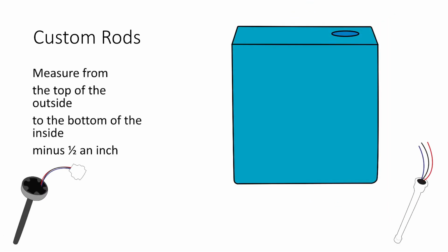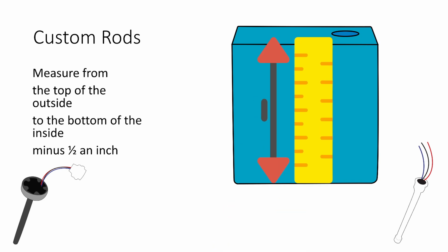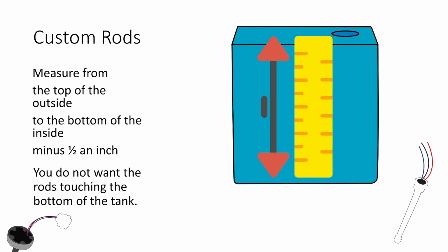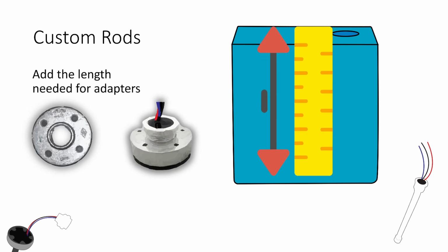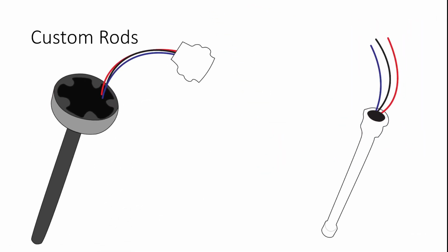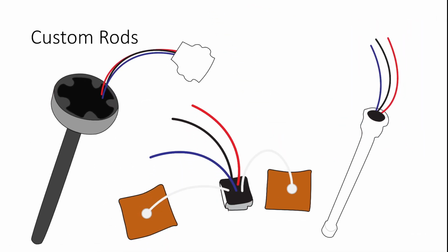To measure the height of the rod, measure from the top of the outside of the tank to the bottom of the inside minus about ½ inch. You do not want the rods touching the bottom of the tank. Please take into account any adapters you may need to install a 1-inch pipe thread for the PVC rod. All rods have the same 3 wires as the Moda sensors. They are connected and calibrated the same way.